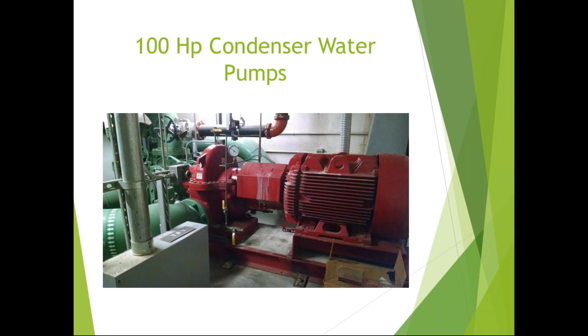It has secondary and primary loops. The primary loop is only 3 stories tall, from one mechanical floor to another. The secondary loop goes from the 1st floor all the way up to the 49th floor, about 650 feet. So we have approximately 315 PSI head on the bottom floors.